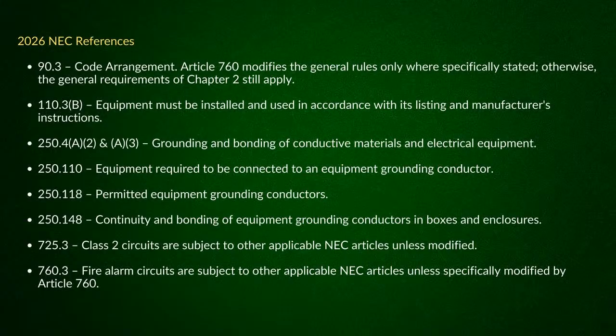It makes more sense when you look at why I've got it laid out this way in my code book. The first thing I do is code arrangement and talk about Article 760, because you get into your permitted equipment grounding conductors in 250.118, and then the continuity of bonding the equipment grounding conductors and boxes and enclosures in 250.148. But then, this is where you come in. When you're dealing with Class 2 circuits, they're subject to what?